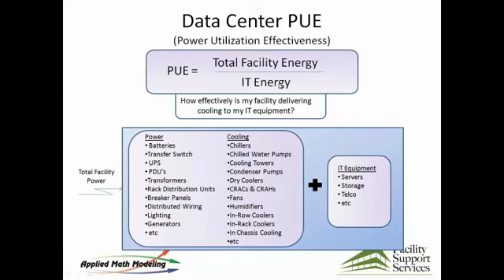That's correct. Generally, what we find in the data center is it's too cold. People are running them too cold, and they're blowing too much air. That's often what we find. So trying to drive up supply air temperature can save an awful lot of money. Open the window of the economizer if you have one, and trying to increase overall temperature in the room is generally a good thing.